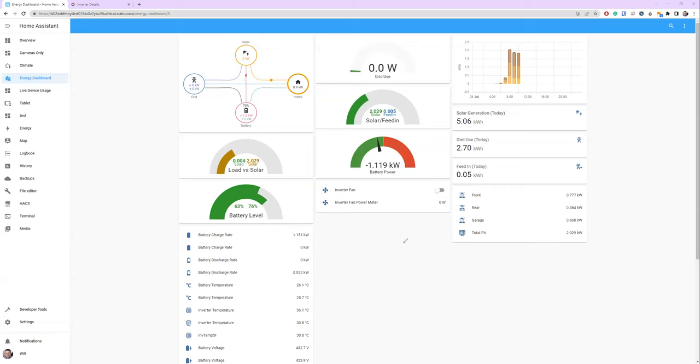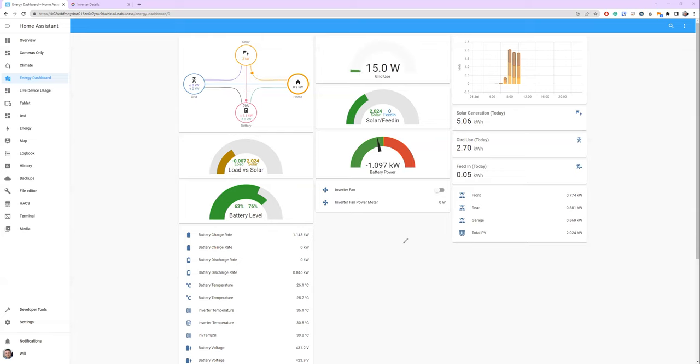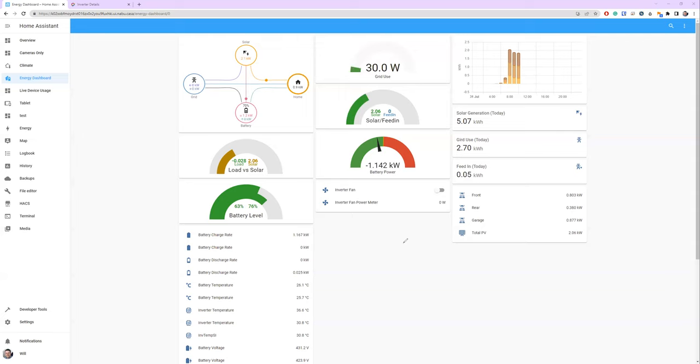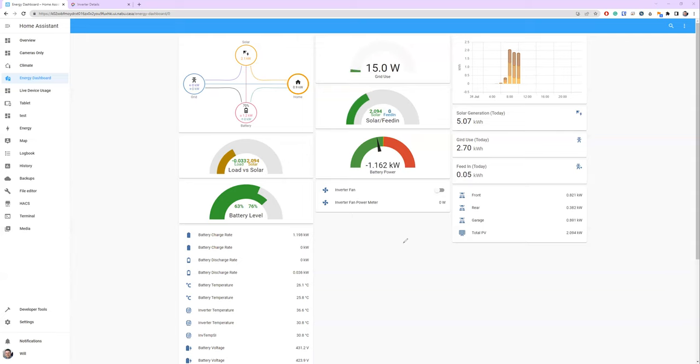Now I'm going to turn the water heater back off, and now suddenly the feed-in has shot up to nearly three kilowatts. The grid is overcompensating and it all stabilizes again. You notice the battery goes back to charging again. So if a load such as an oven, a kettle, an electric hob, if any load is turning on and off - it's particularly bad with hobs, ovens, and kettles - what's going to happen is as that element turns on and then turns off, especially if it's an oven or a hob, you're going to see those blips. You're going to see suddenly grid usage and then you're going to see grid feeding, or vice versa.